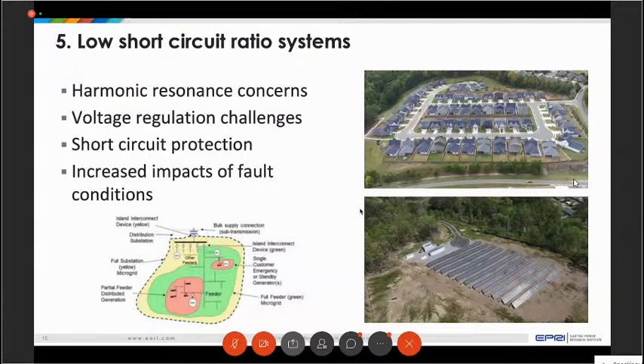All of our power quality benchmarking has been around measuring and characterizing voltage, because that's the quality of power we deliver as a utility to the customer. But all of the information about something going wrong, a fault condition, or a problem with a piece of equipment is in the current.